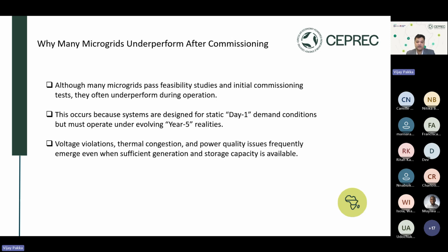So as demand grows, whether within the microgrid or spatially outward outside the microgrid, it becomes more unevenly distributed. So some sections of this network could become overloaded, or it can experience excessive voltage drop. And depending on the customer behavior, how they engage with the electricity, this issue could be aggravated. This could lead to customer complaints, damage to equipment throughout the system, from the point of contact to the main grid to the customer, and even disconnection.